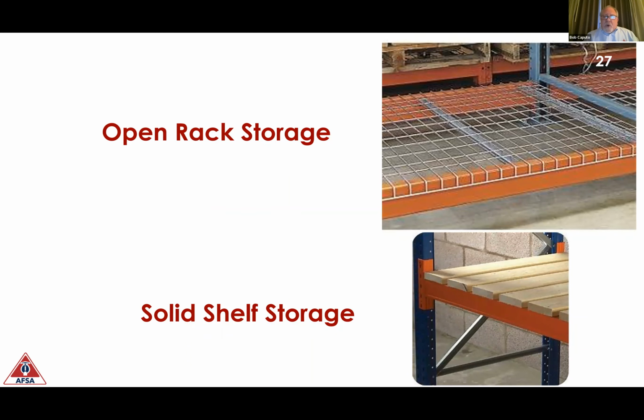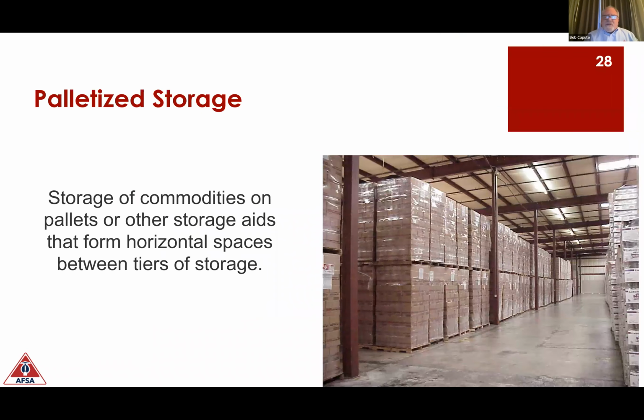So we care if we have open racks versus solid shelf racks. Now, don't assume just because they have wire mesh on their racks that it's open, because if they put the unit loads or the pallets closer than 6 inches apart, they take away the flues and then they become solid shelf storage, even though the pallet rack itself is open. So the material you put on the rack can cause you to be solid shelf, even if you don't have a physical shelf. Again, probably not something you're going to care about, but those are the things we're going to have to discuss with your client to ensure that the building matches their need, or that the fire sprinkler system within this building matches the need.